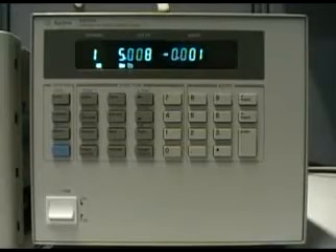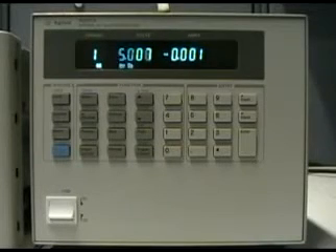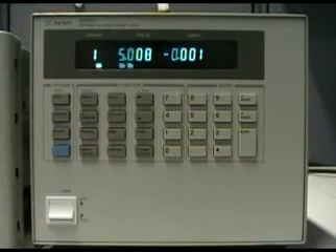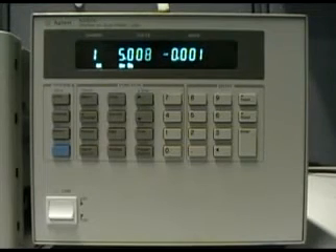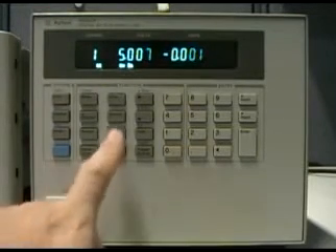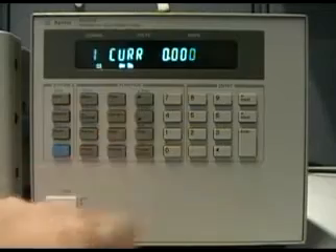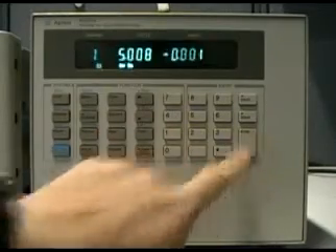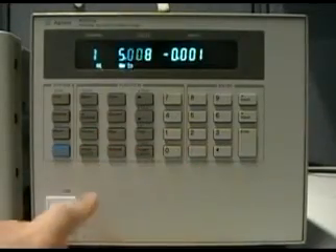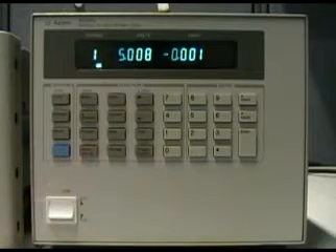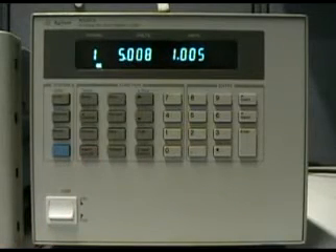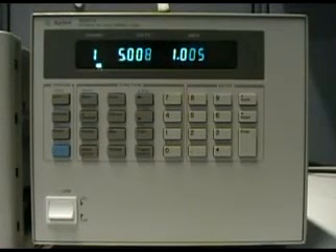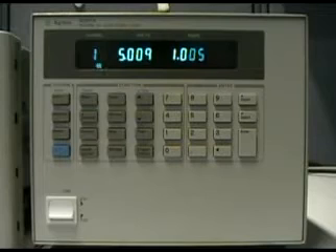Next we program the N3300 electronic load. We start by programming a steady state of 1A. We go to Current, 1, Enter. Then we turn on the input. Now you'll see the electronic load is pulling 1A from the DC power supply.